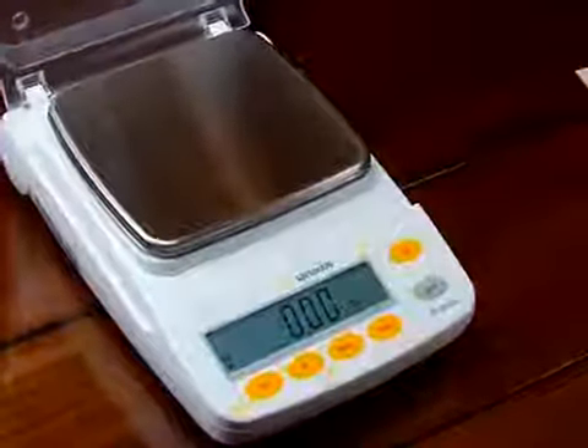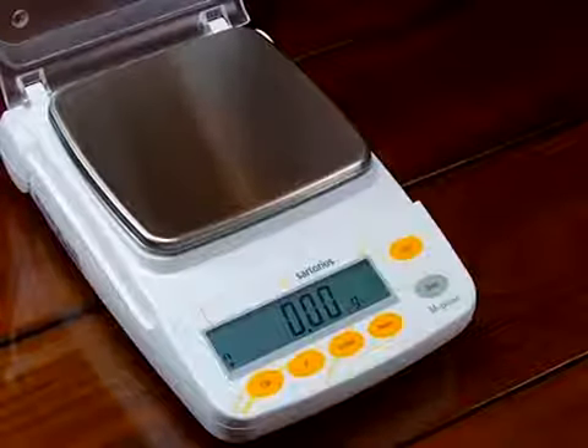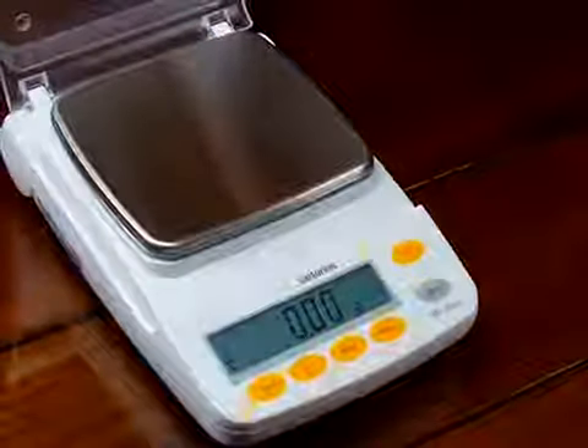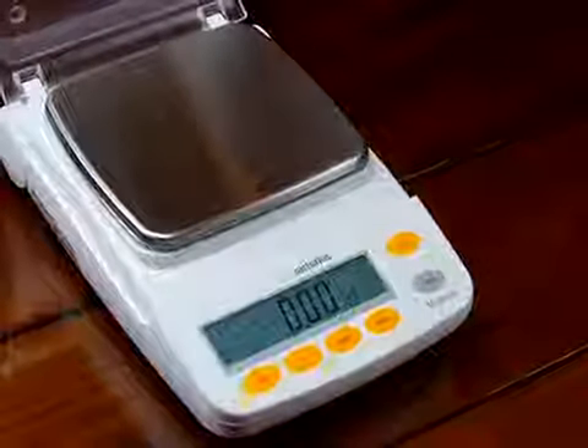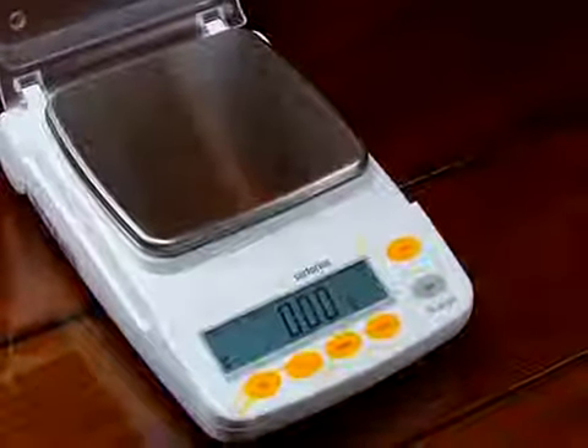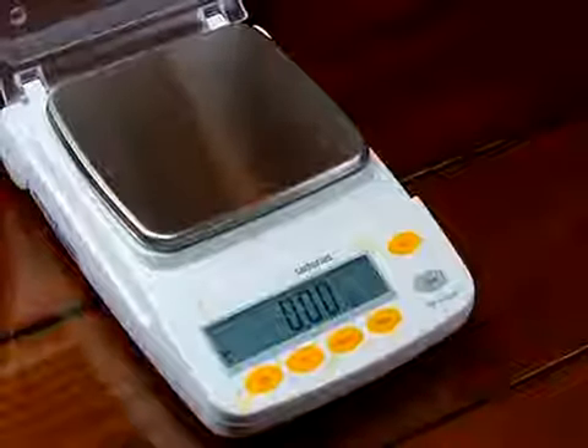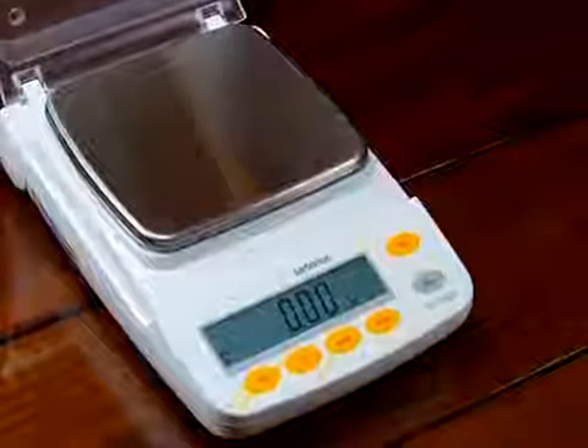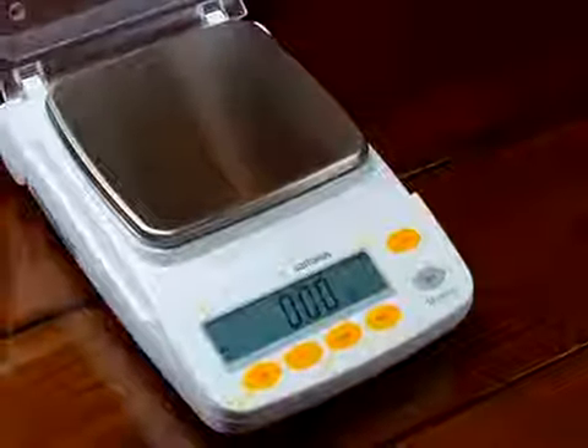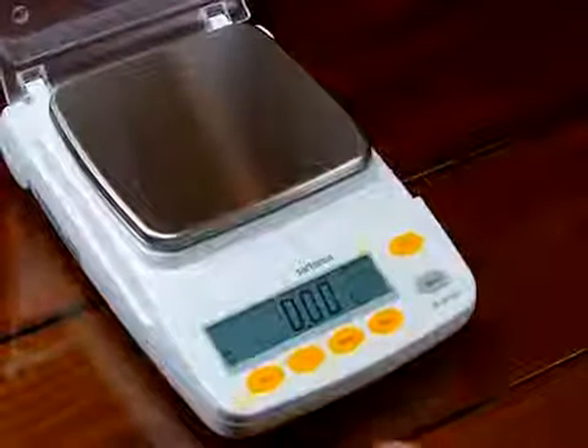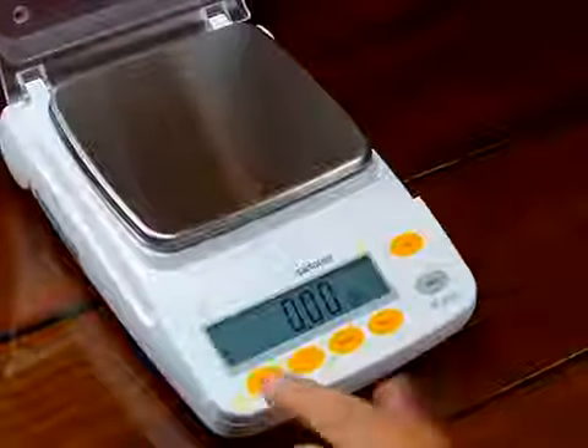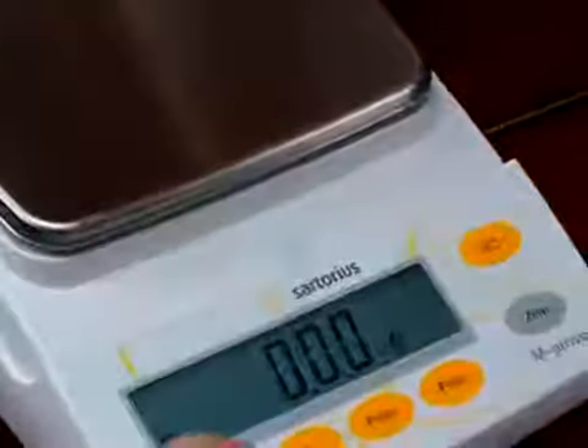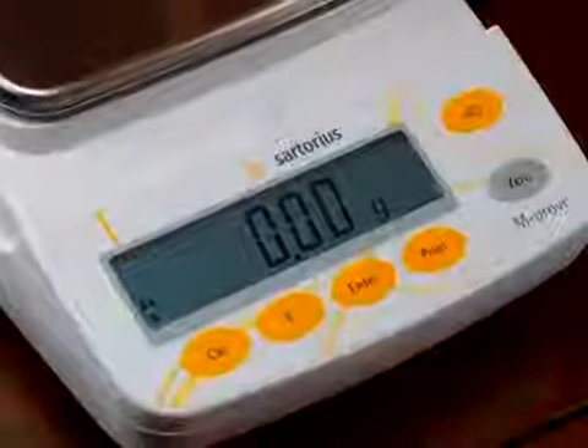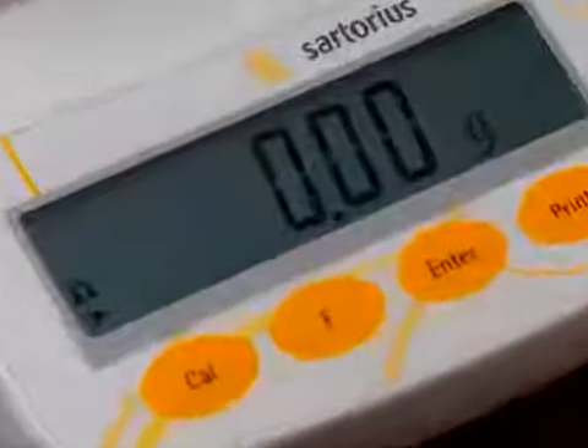So let's go over how to calibrate the balance. Another reason for calibrating a balance is that everywhere in the world has a different magnetic north. So balances should be calibrated, and the manual says to calibrate the balance before putting it into service. As I mentioned, the balance should be level, which it is, and you want to turn on the balance. You'll notice in the left-hand corner there is a symbol that looks like a balance beam with two weights hanging. This is your stability indicator. Before doing the calibration, your balance should show that it is stable.